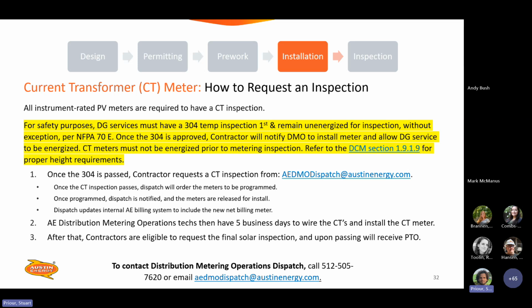Please refer to 1.9.1.9 in the design criteria manual for height requirements. Height requirements being 30 inches minimum to the bottom of the enclosure, and I think up to like 96 high. So you have a berth there, but it's going to be off the ground at least 30 inches. Once the 304 is passed, you can request a CT inspection using that email address there. The AE metering team, their technicians, they have 5 business days generally to wire the CTs and install the CT meter. After that, the contractors are eligible to request the final solar inspection, and upon passing, will receive PTO.